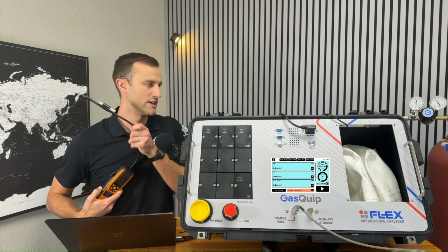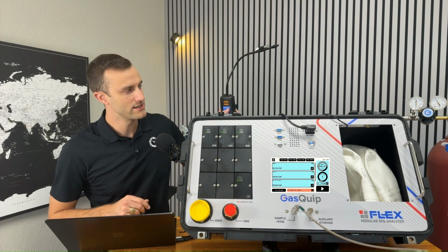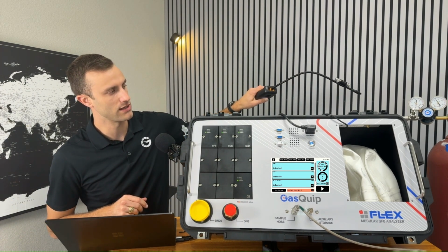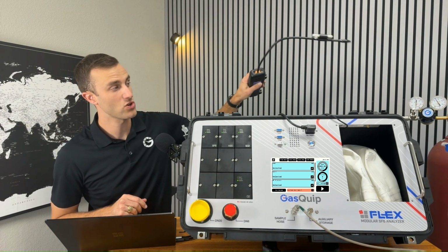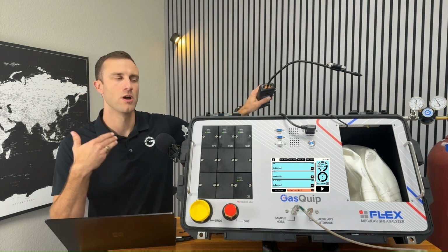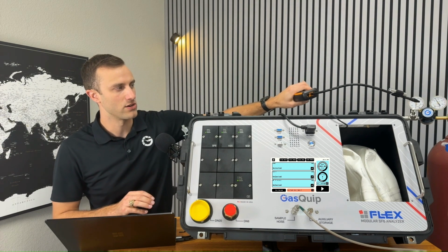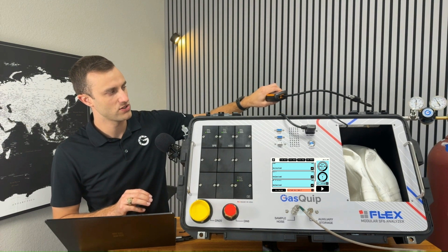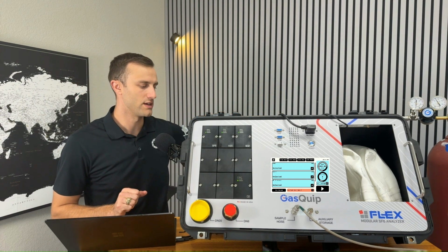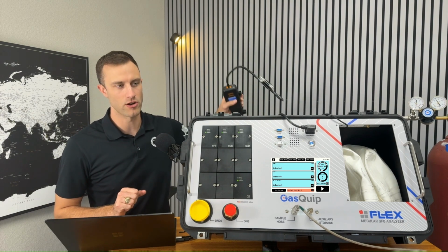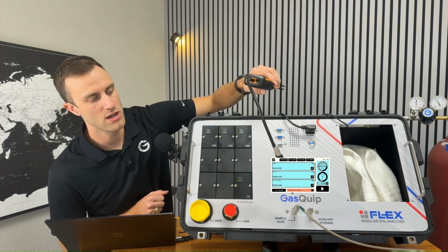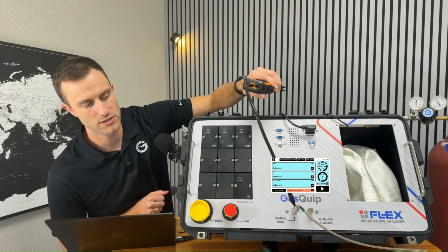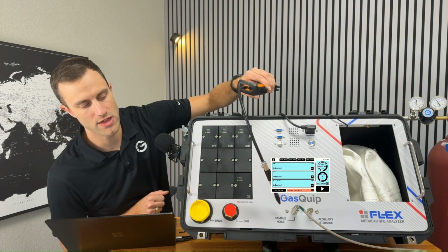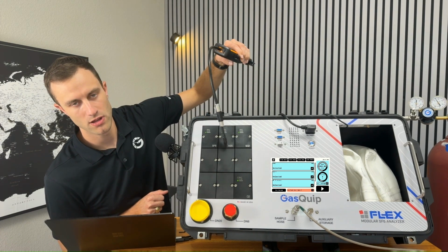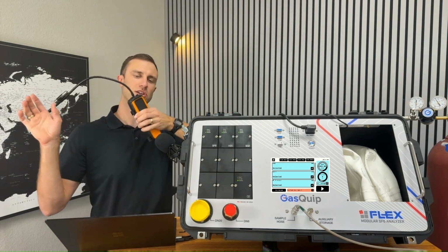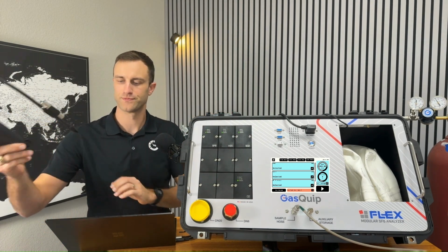What I would like to do is run our leak detector along the length of the hose, starting at the connection point at the breaker or at the gas cylinder, and just sweeping slowly across the length of the hose and the regulator, and also our connections here at the front, starting with the input fitting, and then also testing around the modules and making sure that there's no leaks there.